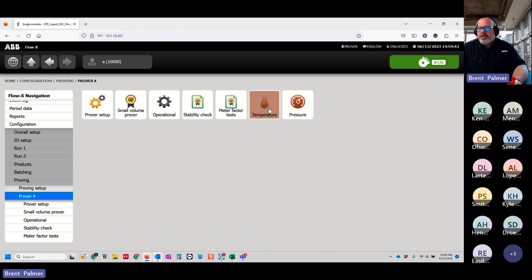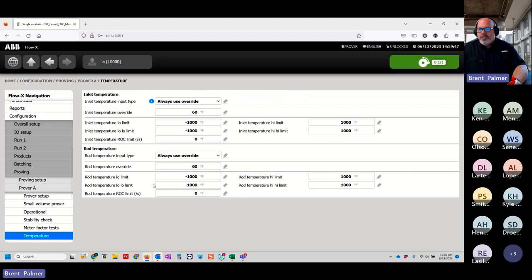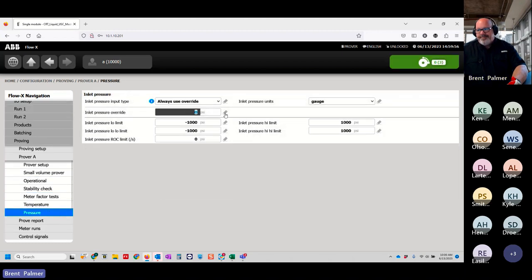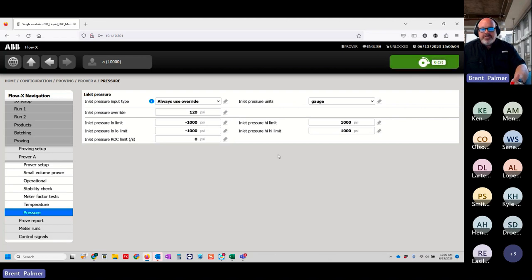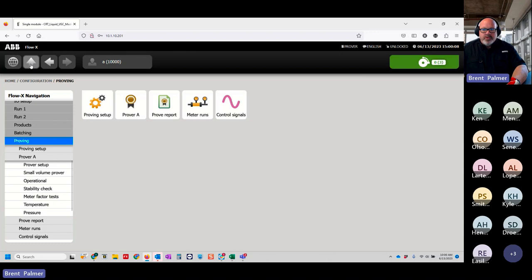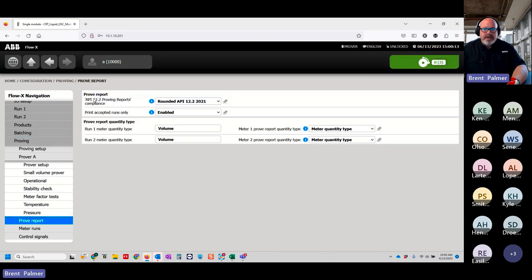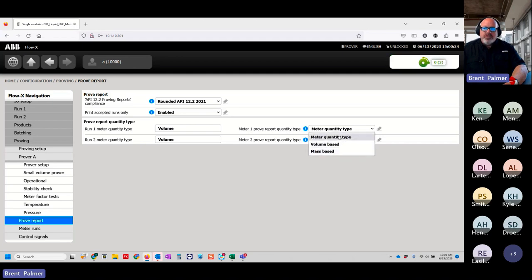Coming back up, under temperature and pressure settings, I said we're always using override, so I'll keep temperature at 60 degrees, rod temperature at 60, and pressure at 120 psi. That completes our configuration. Going to the proof report settings, I can set compliance with API 12.2, whether to print only accepted runs — since templates are set up for 10 runs — and the report quantity type: meter quantity, volume-based, or mass-based. This allows you to prove the flow computer as a mass meter.